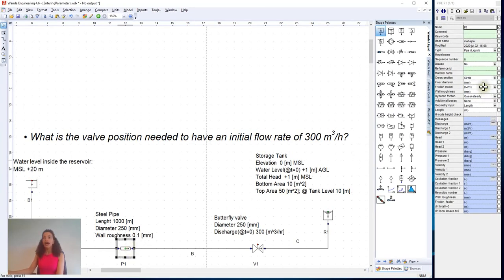which has an inner diameter of 250 millimeters, a roughness of 0.1, and a length of 1000 meters. We can also insert one kilometer and press enter. By doing so, WANDA will automatically convert kilometer to meter because the unit setting is currently in meters.